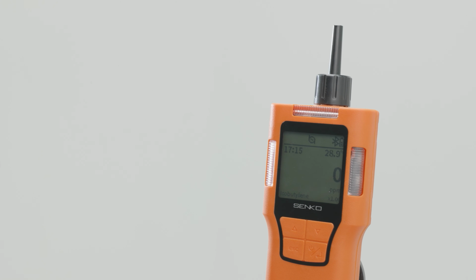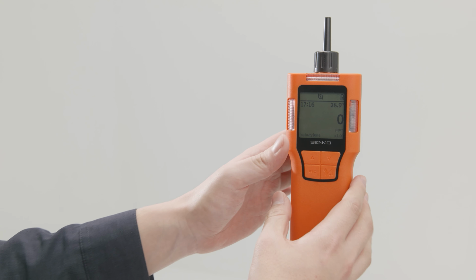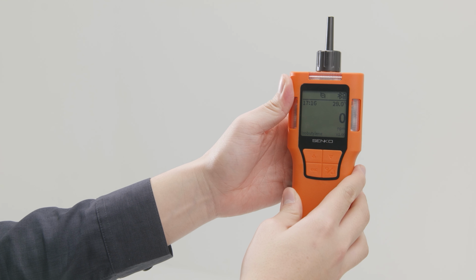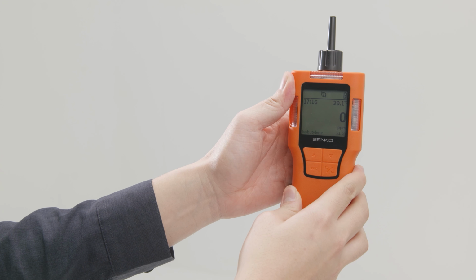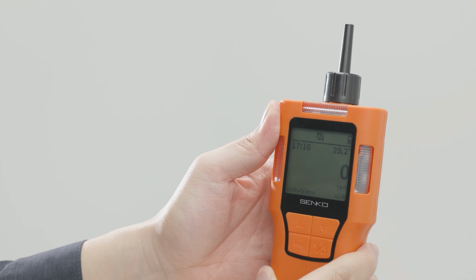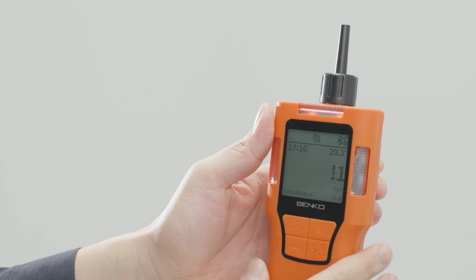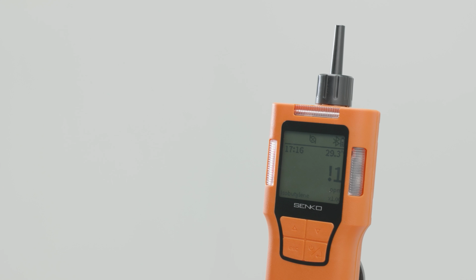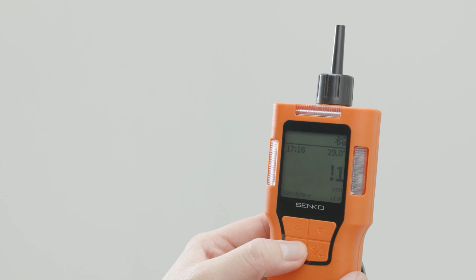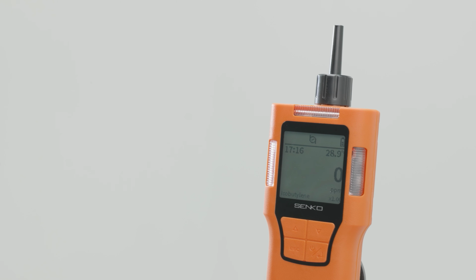vPro continuously monitors the operating status of the built-in pump to maintain accurate gas sampling. If the gas intake path is blocked or an abnormal flow is detected, the LED and buzzer alarm operate at 1-second intervals to immediately notify a pump malfunction. In normal status, the pump alarm does not occur, and if there is an abnormality in the pump, a pump shutoff error is displayed on the screen so that the user can quickly check the sampling issue. When a pump alarm occurs, the user can press the ESC button to acknowledge and release the alarm, and the device clearly displays normal operating status or pump shutoff status. Through this function, vPro prevents measurement errors due to gas inflow issues in advance and always maintains a reliable sampling status.